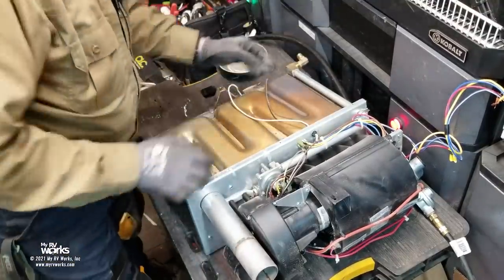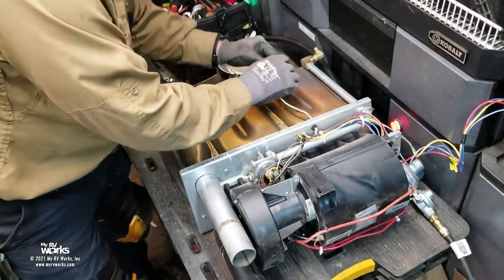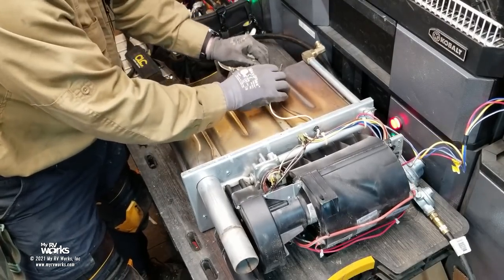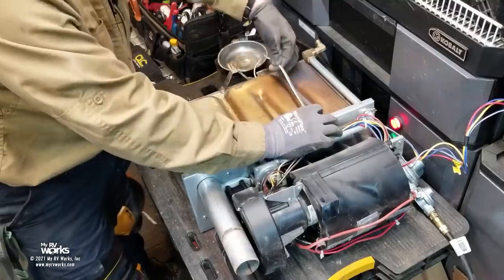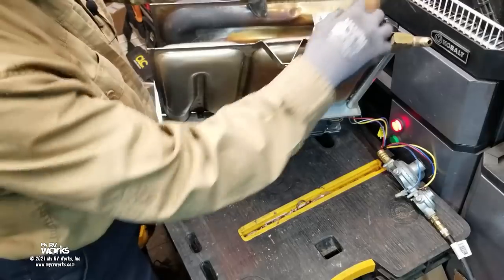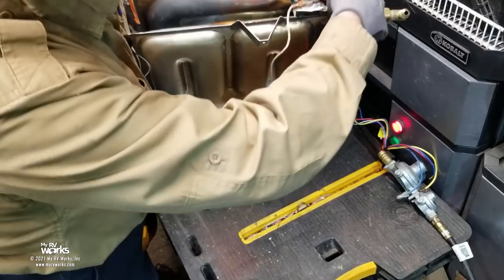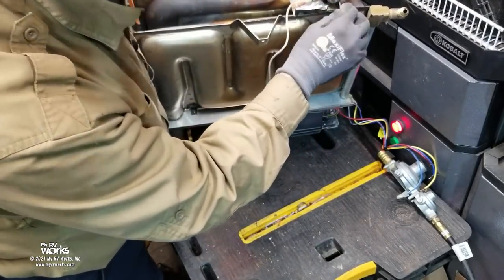Now I'm looking at the wires. I don't see any frayed wires. There's something causing a weird bend in one wire here, but it's not nicked or cut — so these wires look good. These wires are exposed to some heat. There's another kink, but no nicks or cuts. We're doing an inspection and looking for all of this kind of thing.